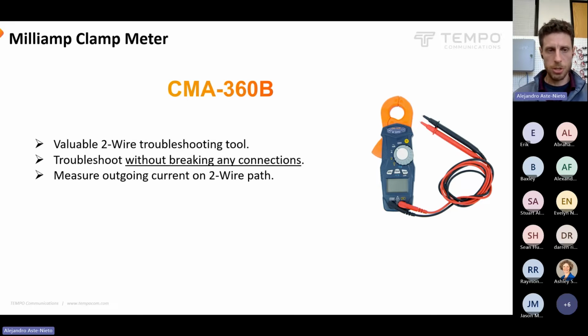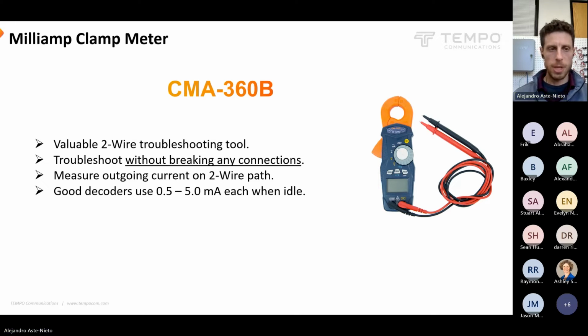materials. So the way it works is you measure the outgoing current on the 2-wire path, and then you can sense what's happening downstream. Good decoders, depending on the manufacturer and type, typically use somewhere in the range of 0.5 milliamp to 5 milliamps when they're idle. When they're operating a zone, they'll use more, but it's best to do your measurements when a system is idle, and look for these consistent numbers. Obviously, a system will all be using the same manufacturer of decoder, as they are not compatible from one to the other. But even one manufacturer will have one system that needs one kind of decoder and another system that uses another kind. So decoders are going to be very consistent in your system, and they will use a consistent amount of current each. And we can use that to our advantage when we're taking measurements and doing some math.